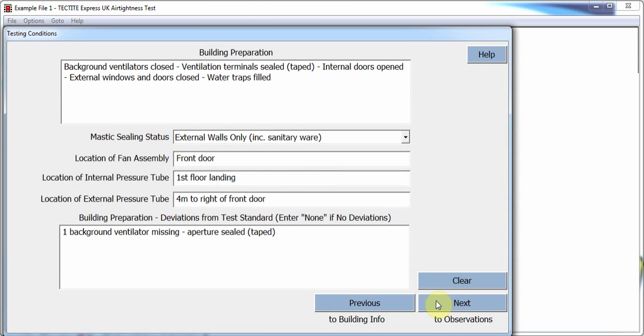The test conditions page allows the user to record the condition of the building under test and the location of test equipment. The building preparation field should be used to note how the building was prepared for the air tightness test, including any valid temporary seals. The building preparation deviations from test standard field must be used to record all deviations from the test standard in relation to the building preparation, including any invalid temporary seals.